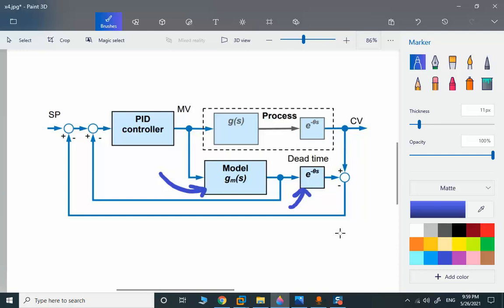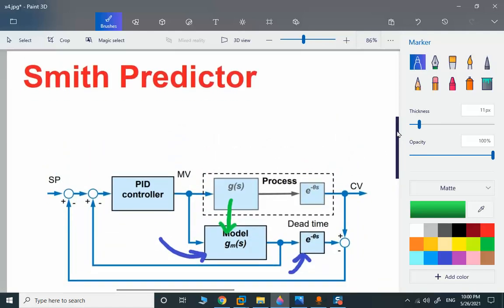Once we find the time constant, gain, and dead time, we can implement this structure in software. The control blocks represent the main process model without delay, and a separate section represents the dead time only. The part inside the dashed section is in the field; all other calculations are in the programming platform in the DCS. It is very easy to implement — this Smith Predictor structure can be used in Delta V, PCS7, Yokogawa, and all those platforms.